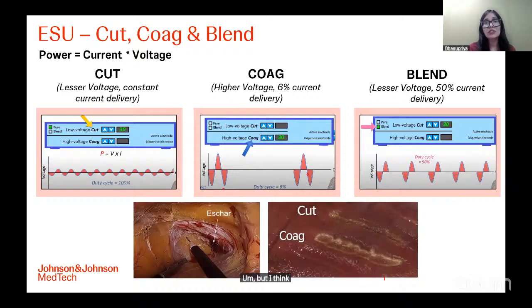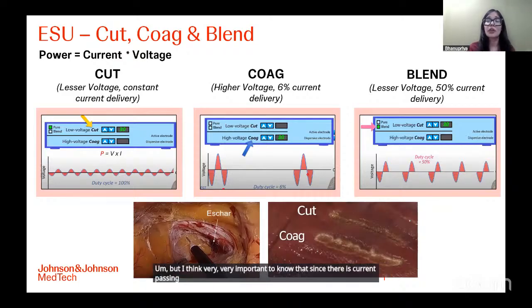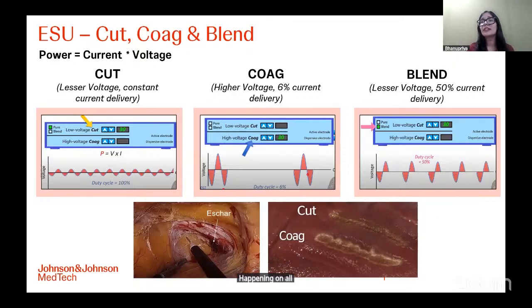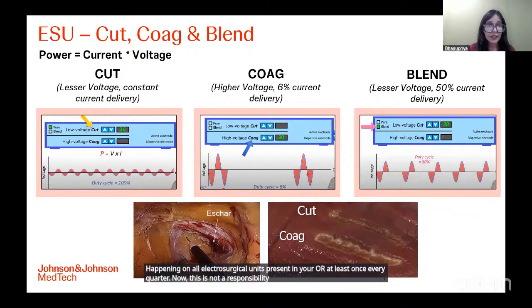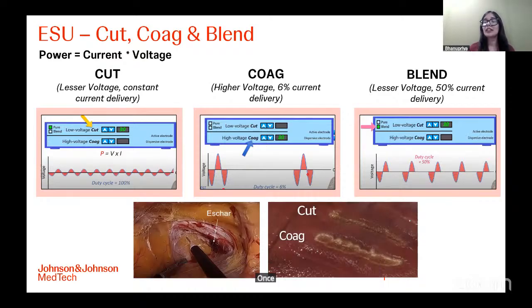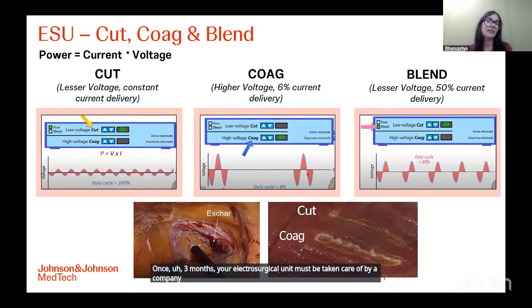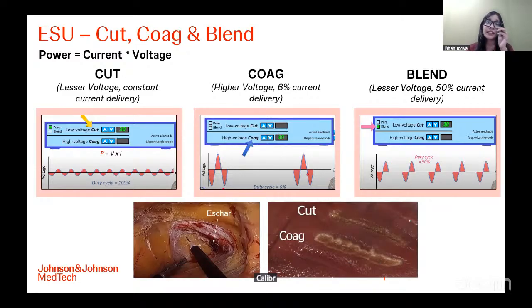But it is very, very important to know that since there is current passing through the patient body, electrosurgical units need to be calibrated, and there needs to be preventive maintenance on all electrosurgical units present in your OR at least once every quarter. Now, this is not a responsibility of a surgeon, but it is a responsibility of the biomedical engineers and the OT technicians in your hospital to make sure that once every 3 months, your electrosurgical unit is taken care of by a company-designated field service engineer who comes there, calibrates the devices, and makes sure that the output level of the device is as per the commitment.